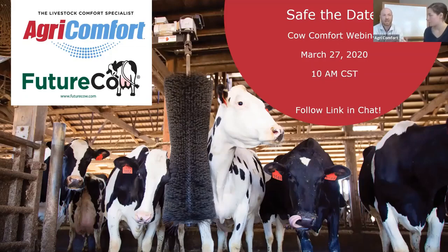The other option is you can try to preheat the air and take some of that humidity down. And that's a good solution, but my only concern is, if we go to heating the air in an attempt to reduce the humidity, inherently the human component is going to say, I'm tired of spending this much money on burning LP, I'm going to turn my ventilation rates down. And to me, lower humidity air with a lower ventilation rate is worse than higher humidity air with a higher ventilation rate, assuming it's not drafty, to keep that air fresh in the barn. Humidity is the hardest thing there is to deal with.